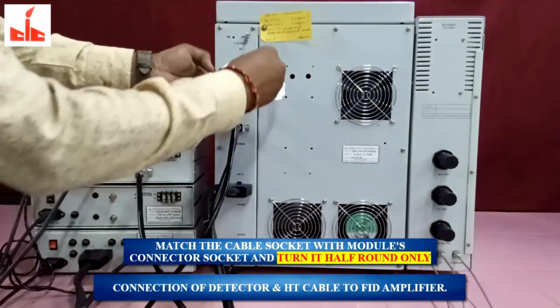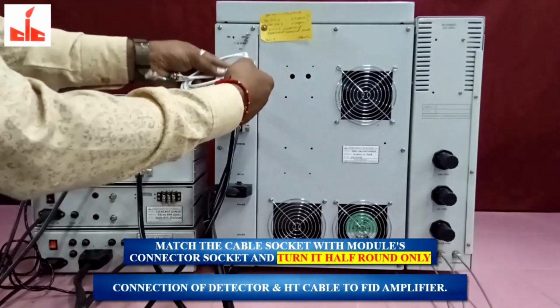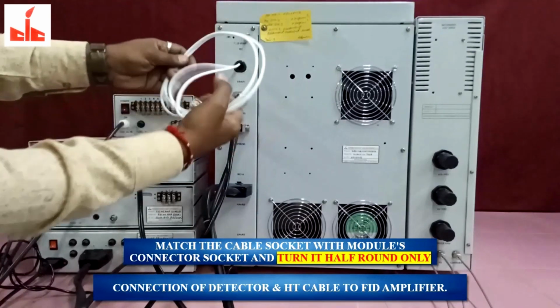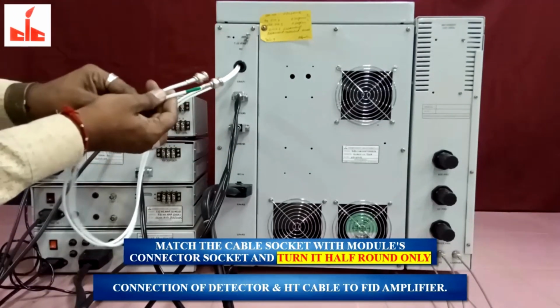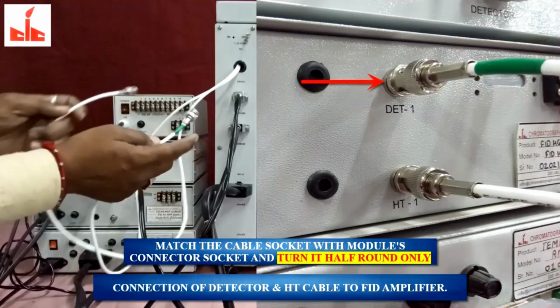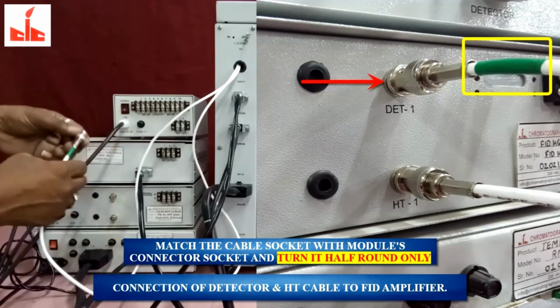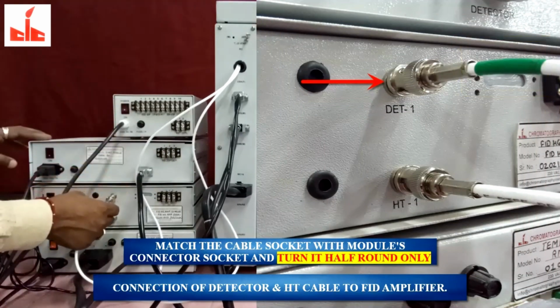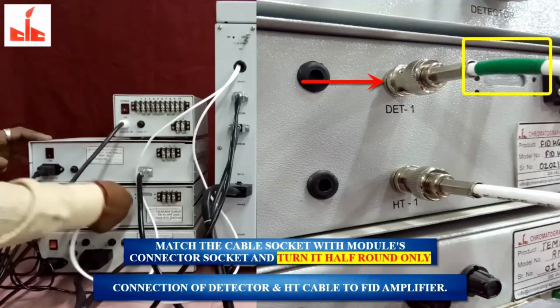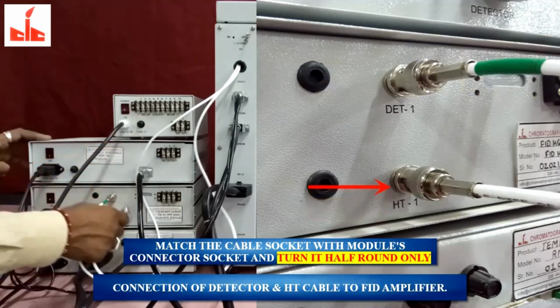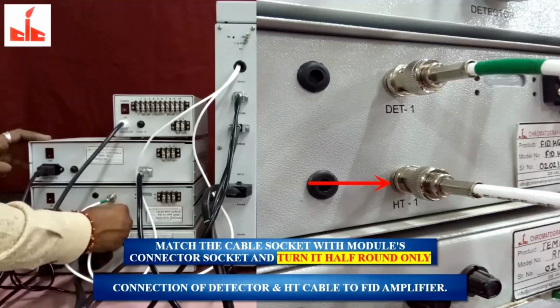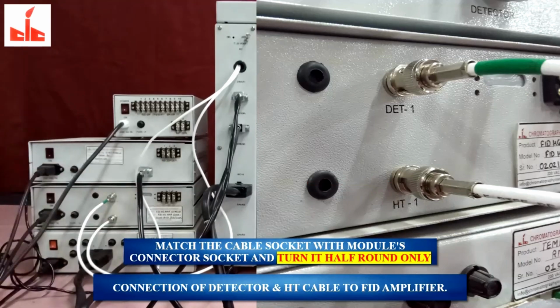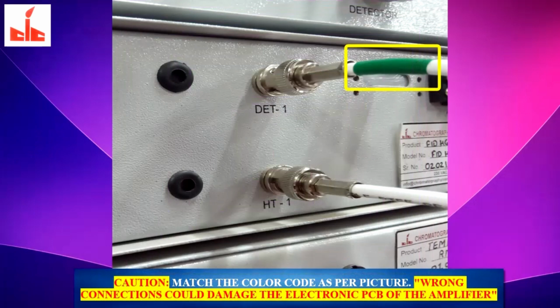Connection of detector cable and HT cable to FID amplifier. Match the cable socket with module's connector socket, and turn it half round only. Match the color code as per picture. Wrong connections could damage the electronic PCB of the FID amplifier.